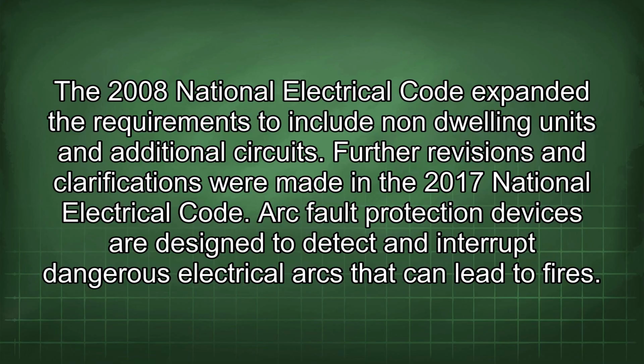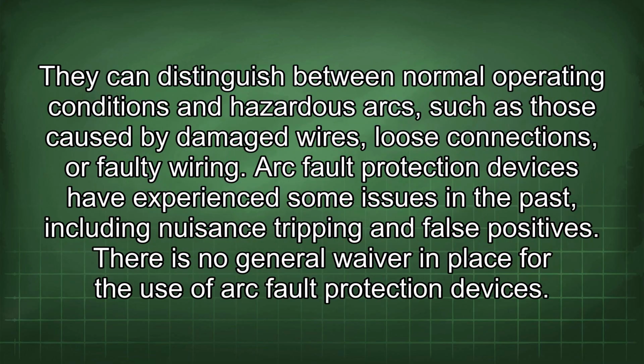Further revisions and clarifications were made in the 2017 National Electrical Code. Arc fault protection devices are designed to detect and interrupt dangerous electrical arcs that can lead to fires. They can distinguish between normal operating conditions and hazardous arcs, such as those caused by damaged wires, loose connections, or faulty wiring. Arc fault protection devices have experienced some issues in the past, including nuisance tripping and false positives.